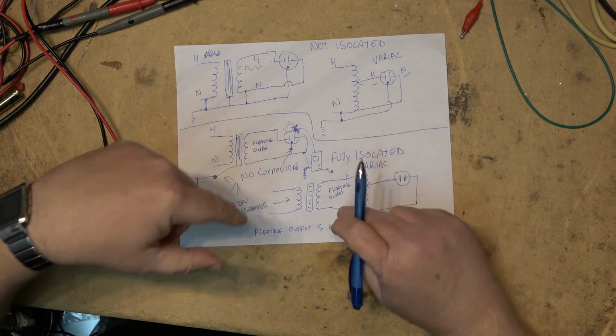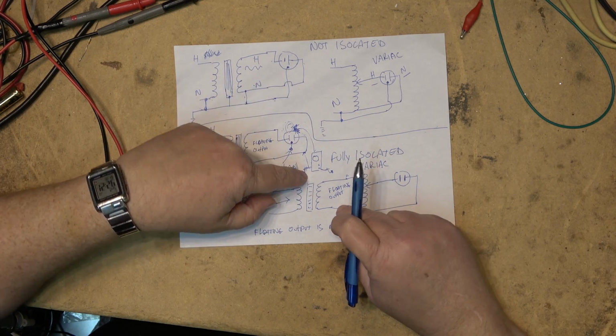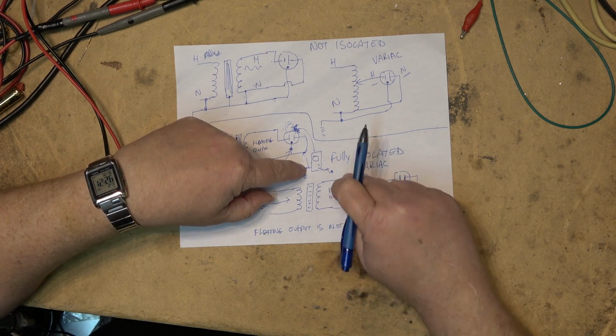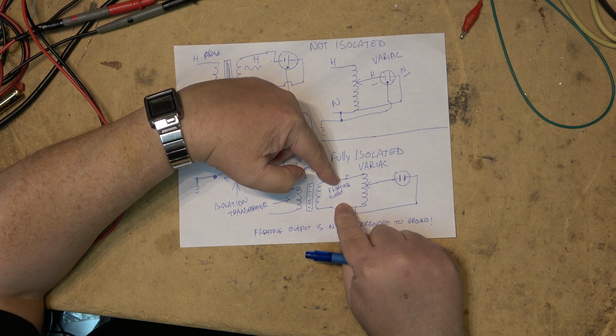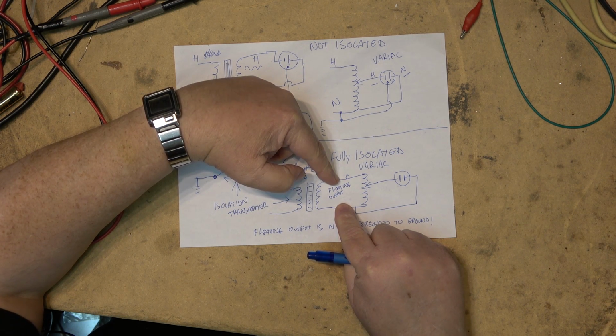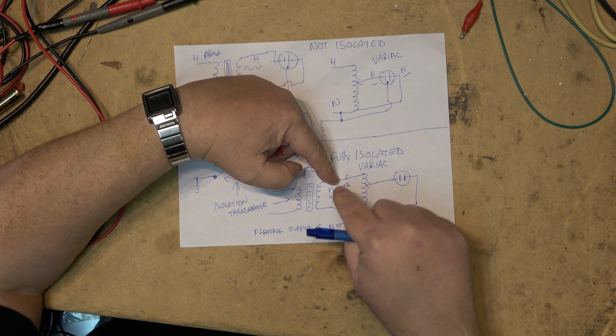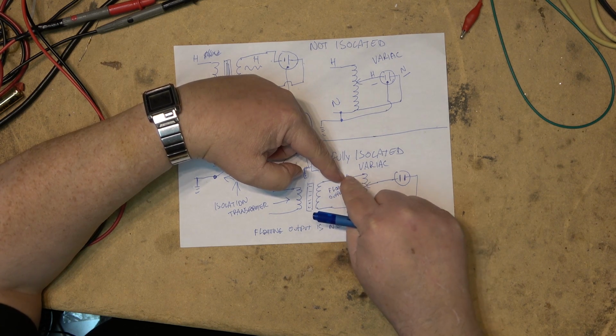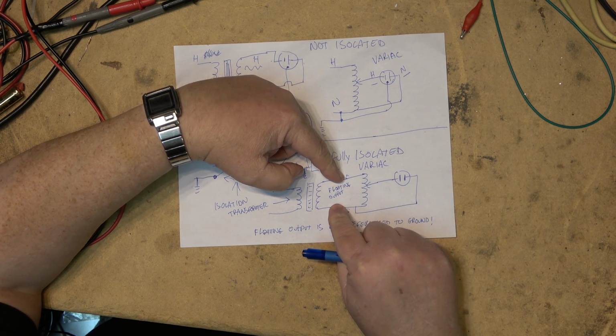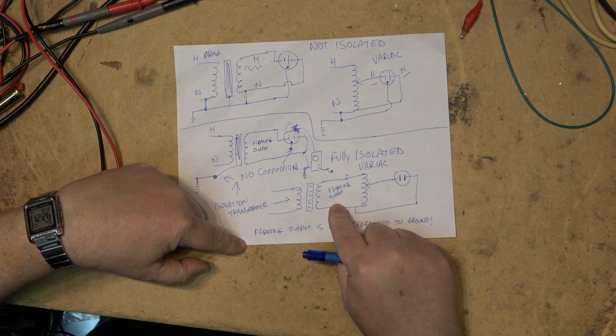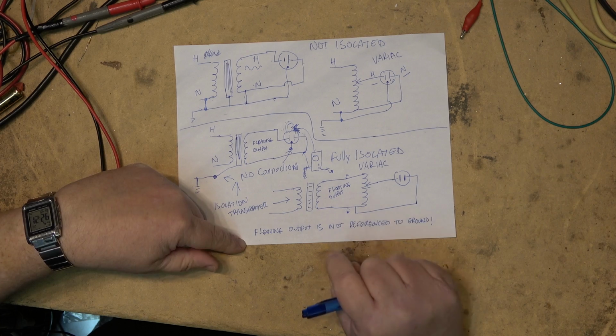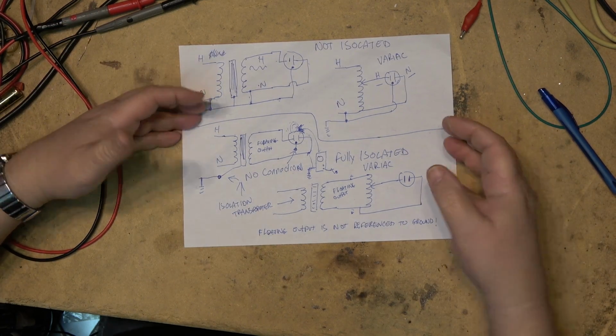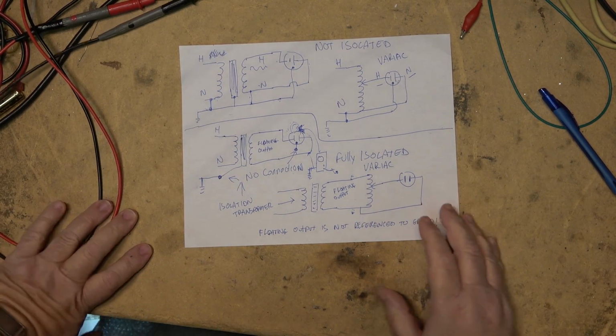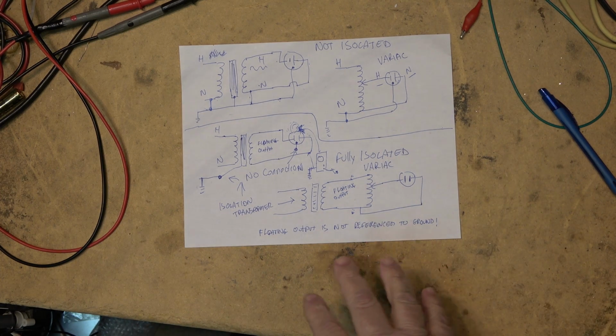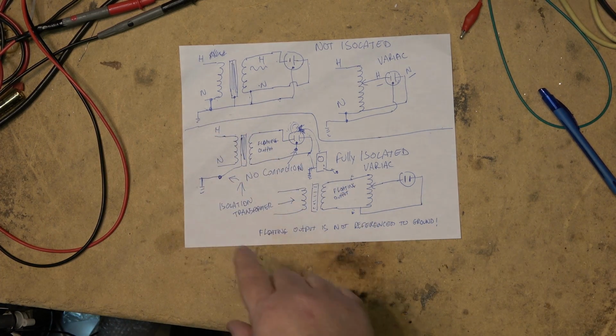Now, if you're touching ground and you touch either side, you will not get a shock. If you were to touch both of these at the same time, yeah, you're going to get a shock, because you don't need a reference to ground. You've just provided the complete circuit to get from one side of the transformer to the other. But from either side to ground, you will not get a shock. You won't even feel it. And it won't trip a GFI either, because there's no current flowing through your body. I thought I made it clear before, but I guess some people need a little refresher. I think that's as simple as I can explain it.